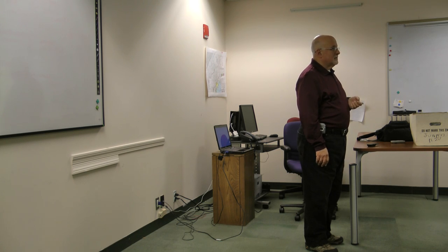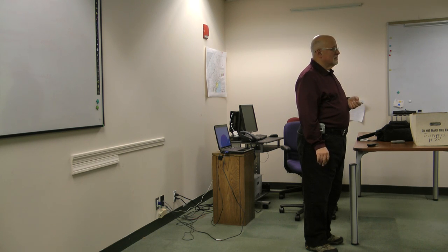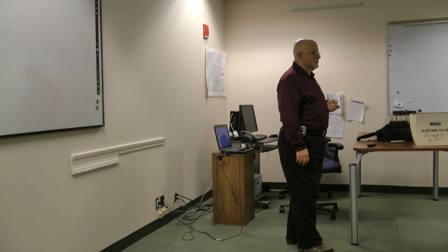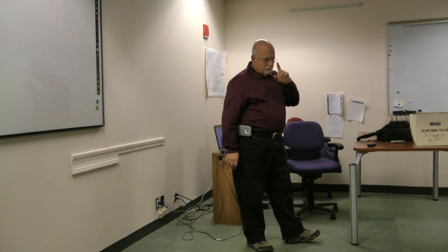Any questions? Andy? One thing that always confused me is all the instructions say ground at a single point, yet the power connector of your grid, as you demonstrated, is connected through the electrical ground system to the service panel, which should have its own ground rod. Is the one point you're grounding to, does that share those ground rods, or is it different? It can be.